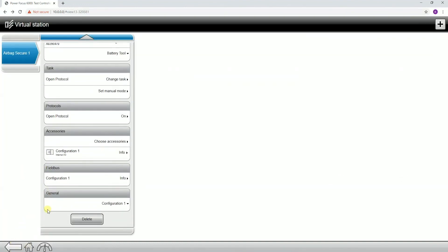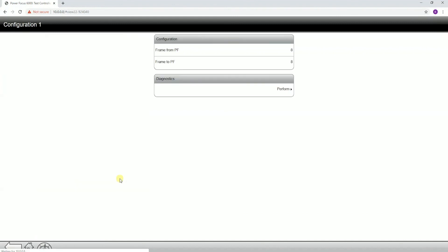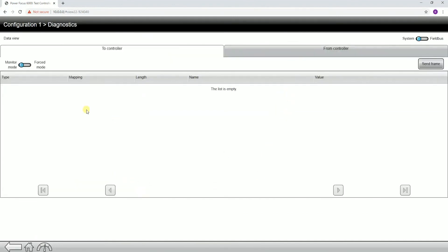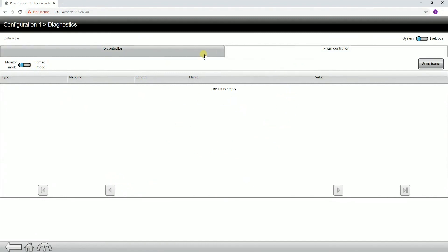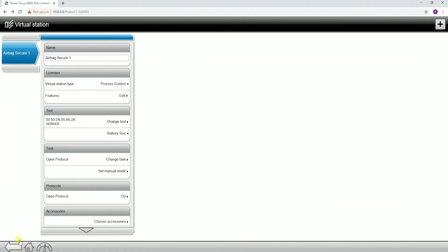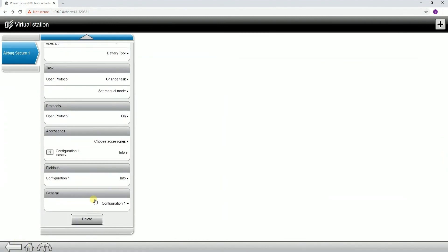Next tab down, we have our field bus tab. If we are using a field bus and it's assigned to the virtual station — this has to be done in Tools Talk 2, and there's a separate video on exactly how to do that. If it is assigned, you can go in here and go to info, where you can view and monitor in force mode the different variables on the field bus configuration. On previous generations of controllers you could never monitor field bus inputs and outputs without additional software, so that's a nice feature on the Power Focus 6000.